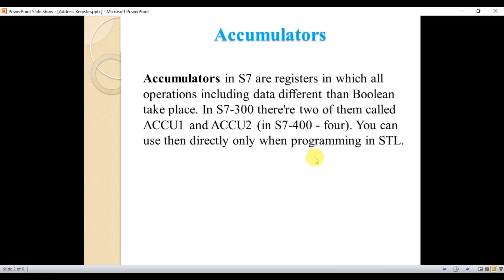The next one is accumulators. In S7, accumulators are registers in which all operations including data different than boolean take place. In S7-300, there are two accumulators: Accumulator 1 and Accumulator 2. In S7-400, there are four accumulators. You can use those accumulators directly only when you program using STL.